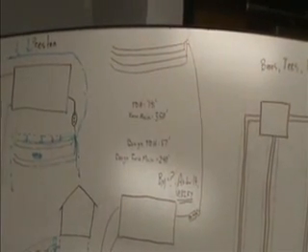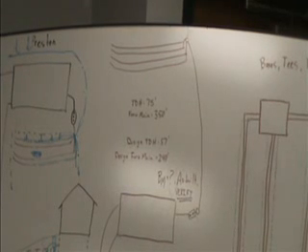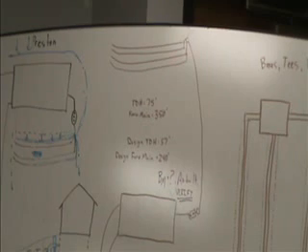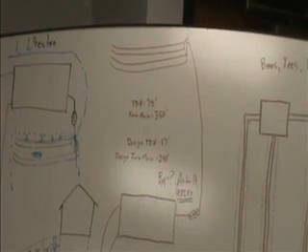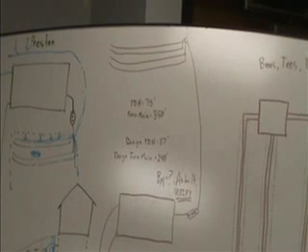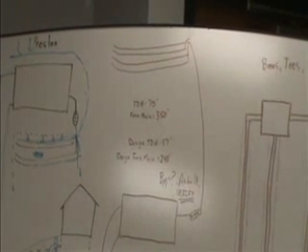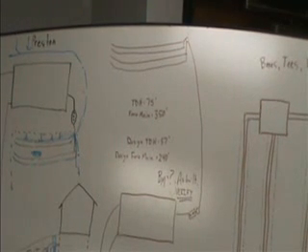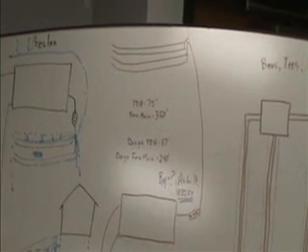Well, the installer dropped the pump from the original design in the tank, and guess what happened? Water didn't get there. Burned the pump up. The pump just sat and ran, and never got to the top. We pulled out the pump curves, and I think the maximum TDH that pump was capable of doing was like 63. So it's never going to get there.